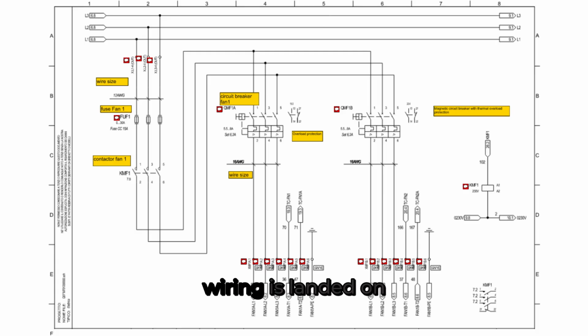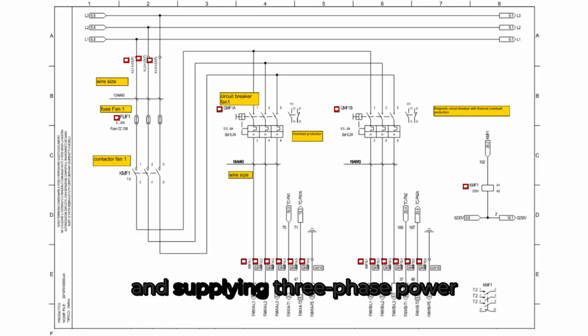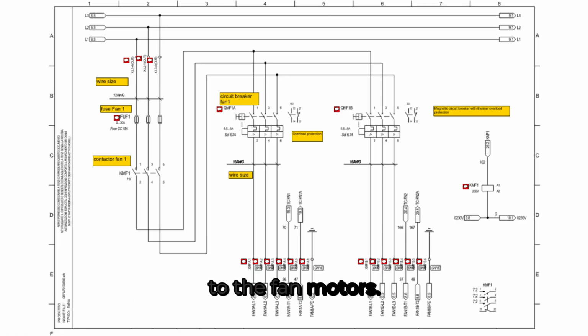Fan motor run status wiring is landed on the terminal block XMF for both fans. Each fan motor has its own terminal markings, helping technicians identify which fan section corresponds to which wire in the field. On the far right side, we see the contactor coil circuit for KMF1, powered by 230 volts. This coil energizes when the controller or thermostat commands the fan to run, closing the contactor and supplying three-phase power to the fan motors.